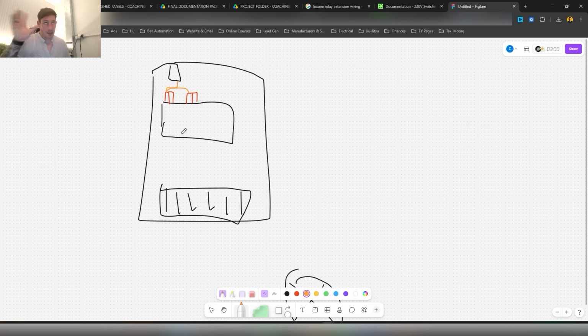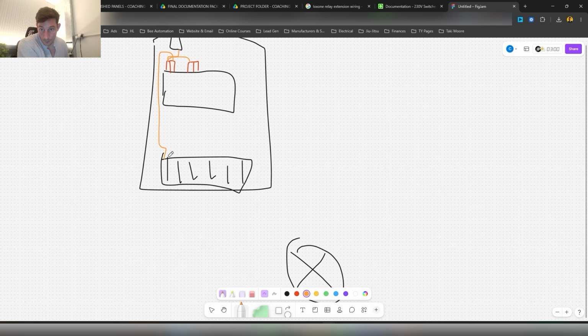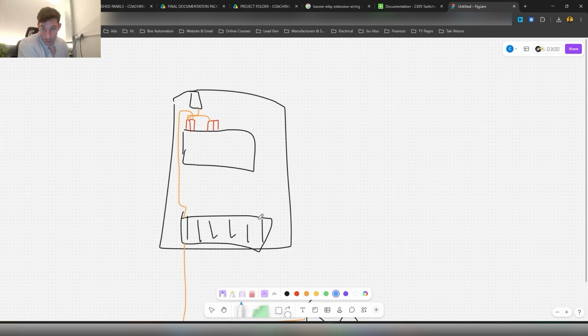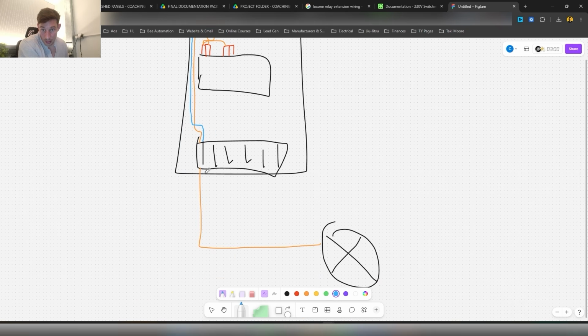In this example, let's say we've got it programmed for the light to come on outside when dusk hits, so the sun goes down. We've also got cables coming out - this is the switch side of the relay going to a terminal block. I won't draw it for this other one, but that's the switch live, going out to the light in the field. With the neutral, we're coming out of the RCBO and going straight over to the same terminal block.